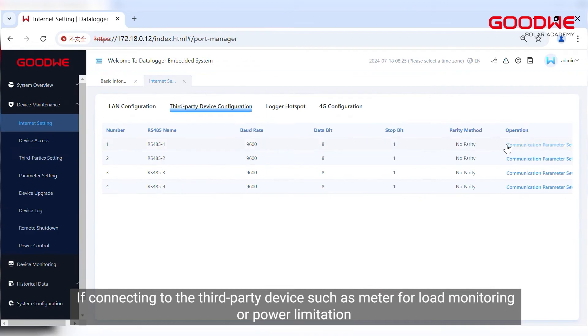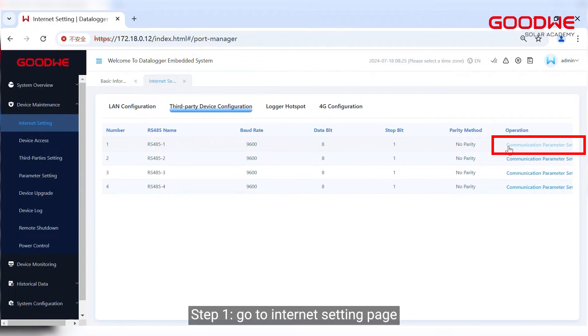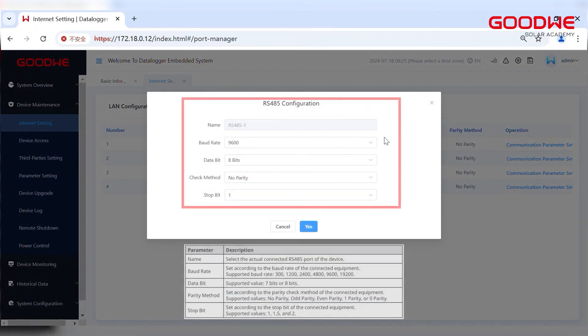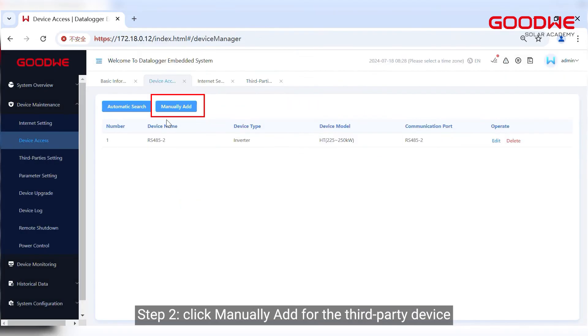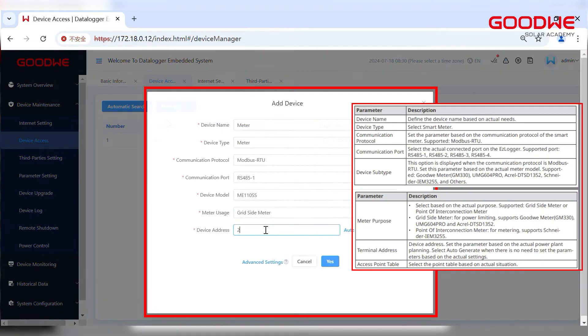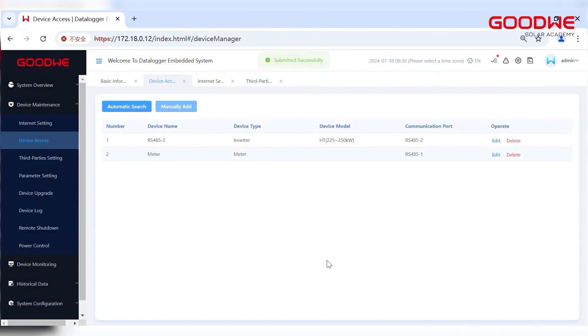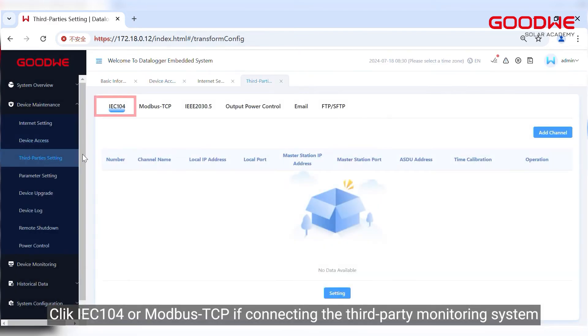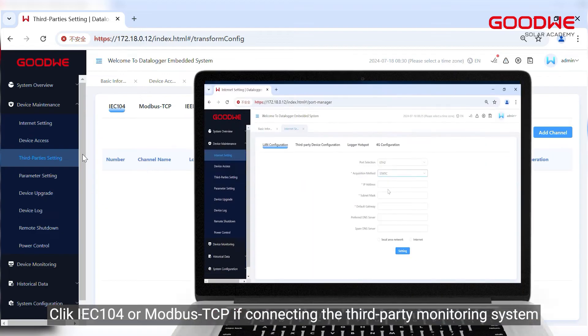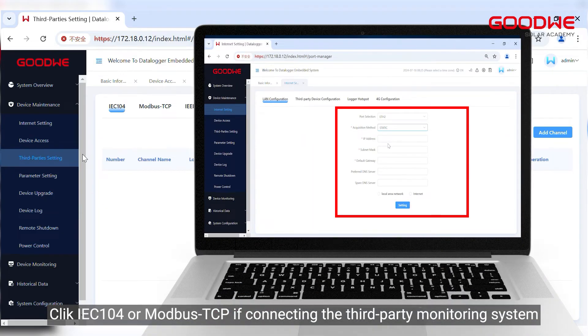If connecting to the third-party device such as meter for load monitoring or power limitation, step one: go to Internet setting page. Query the above data on the third-party device and enter it. Step two: click Manually Add for the third-party device. Click IEC 104 or Modbus TCP if connecting the third-party monitoring system.